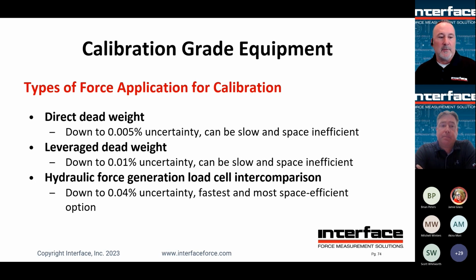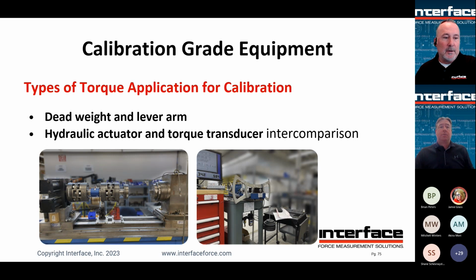And then lastly, we have hydraulic force, which is what Elliot was referring to in one of the previous slides with the hydraulic force load frames that we offer. These are very fast, efficient, and quick ways to perform calibrations, and can get down to as low as 0.04% uncertainty with that type of load frame. Again, here we're talking about torque applications, dead weight, and a lever arm.